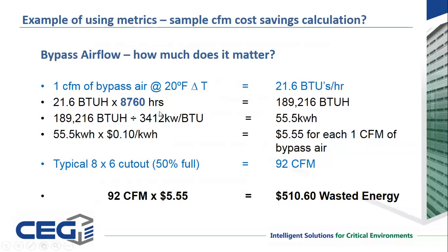When you do the math at 10 cents per kilowatt hour, that eight-by-six cutout that's only 50% full of cables is costing you $5.55 in efficiency. Multiply that out for the annual year — that's $510 just for one cutout. If you've got 100 of those things, this number becomes very meaningful. That's used when people are interested in the return on investment of deploying a mass quantity of floor grommets — you're going to see it on your electric bill. This is just another example of where metrics are used in the industry.